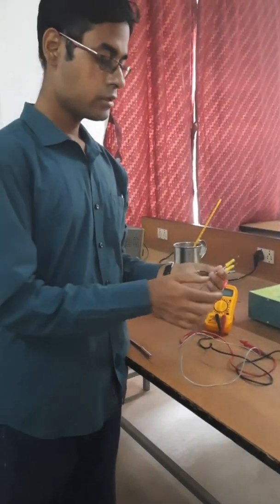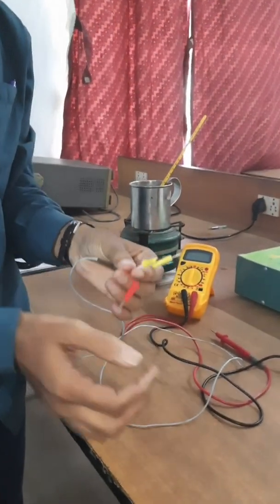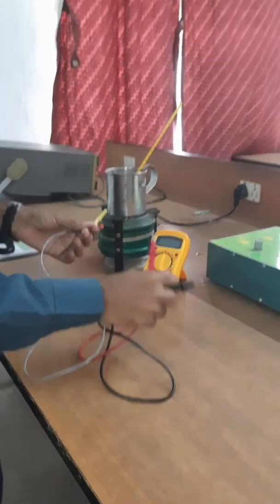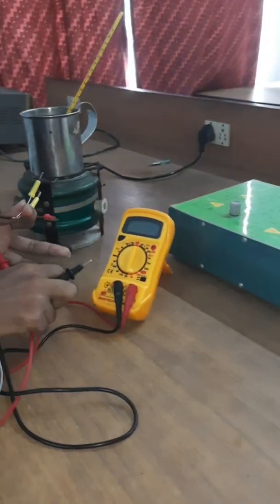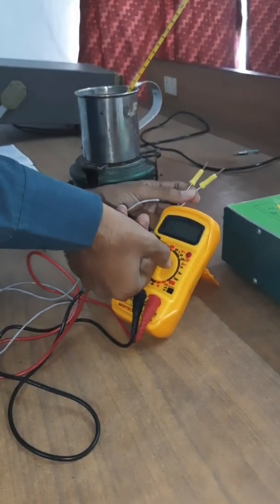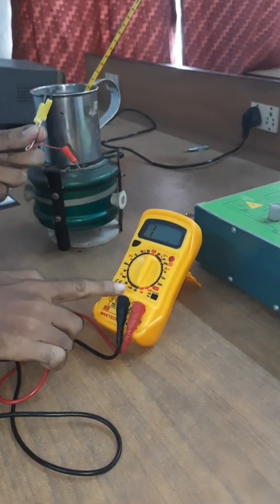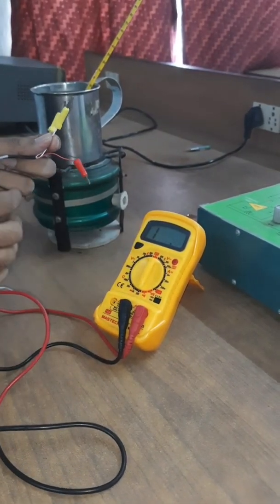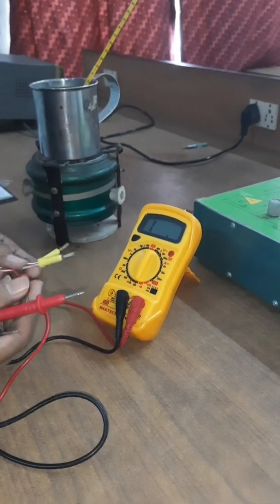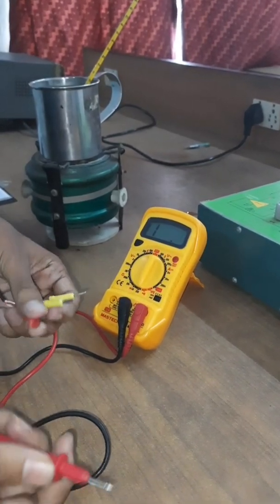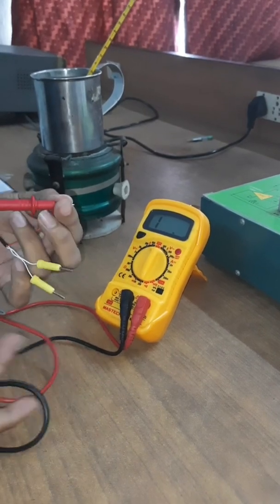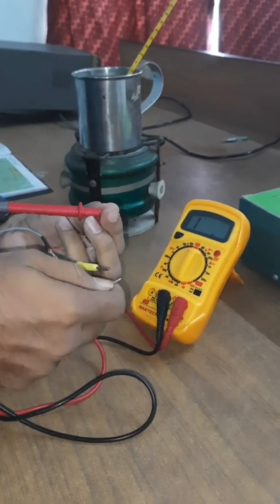If you think of it as a resistance, then we can measure the resistance of the RTD between the red and the white winding. Using a multimeter, we go to resistance, 200 ohm range. This is the 200 ohm setting for the multimeter. We connect red to red and black to any of these whites.